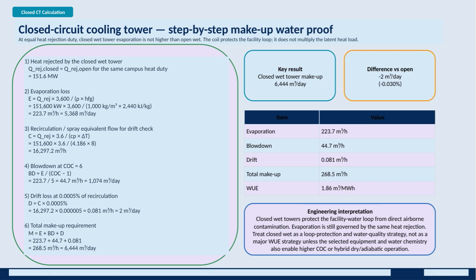From an engineering perspective, closed wet towers are valuable because they protect the facility's water loop from airborne contamination. However, their evaporation remains driven by heat rejection, just like open towers. So, the closed wet tower should be considered primarily as a strategy for loop protection and maintaining water quality, rather than a strong water-saving measure, unless paired with equipment or chemistry that allows higher cycles of concentration or hybrid dry/adiabatic operations.